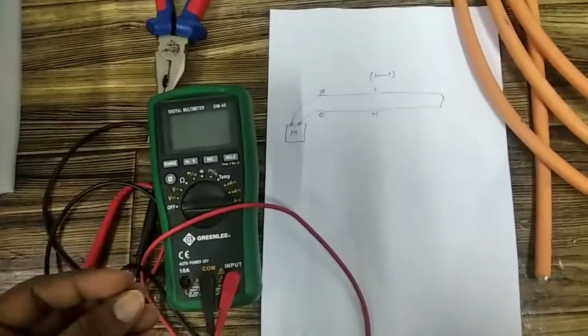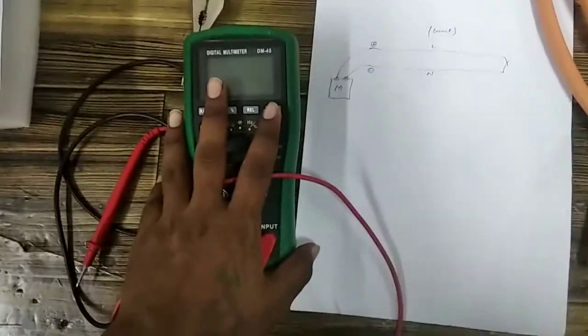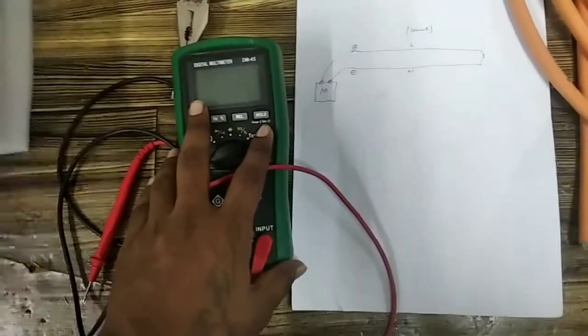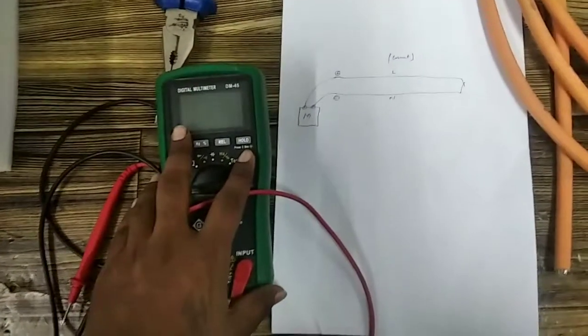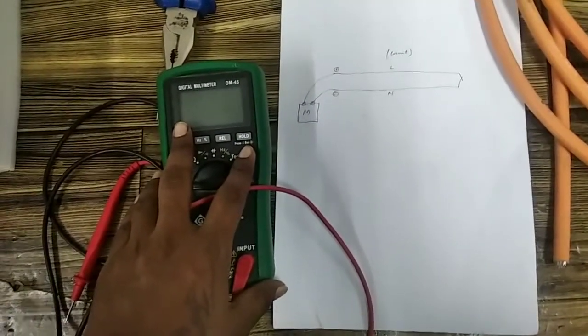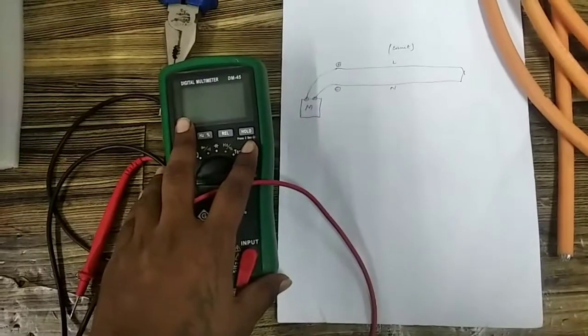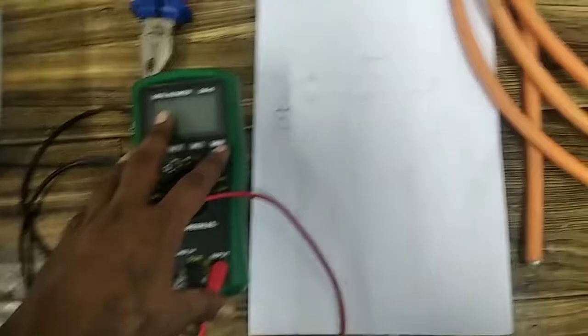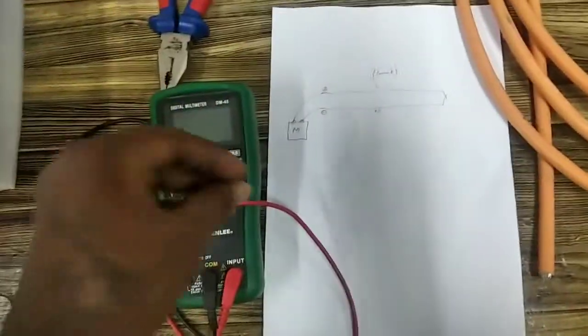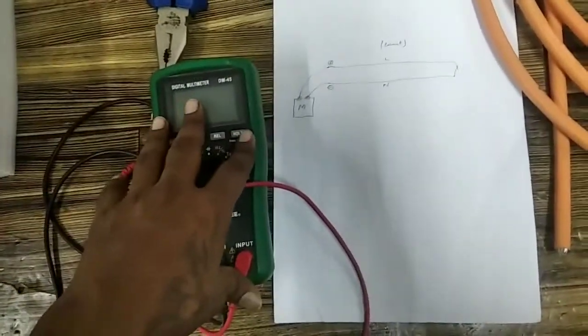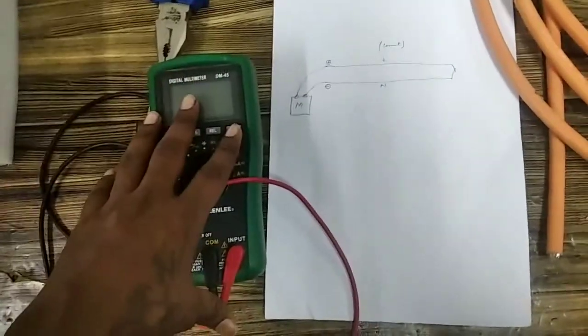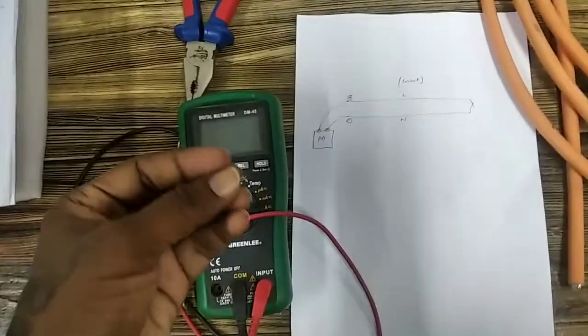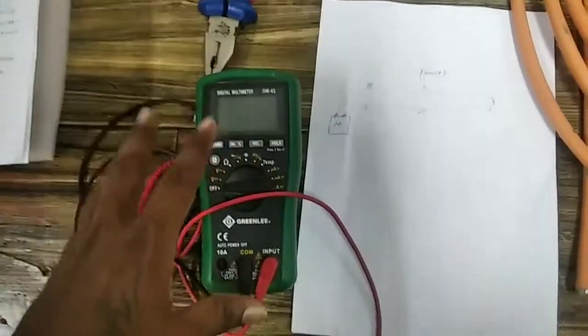During a continuity test, this digital multimeter sends a very small current through the closed circuit to measure the resistance. In any closed circuit there is a very small or negligible resistance. If the value is coming around 20 or 50 ohms that is acceptable and continuity is good. But if it is more than that, it means there is some fault in the cable or the equipment being tested.